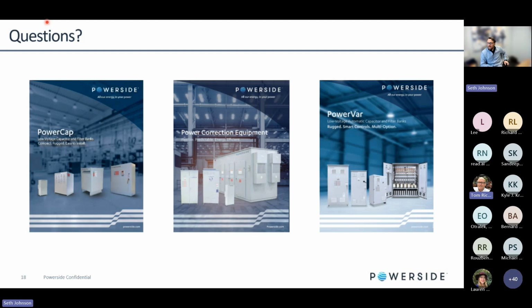Yeah, sure. Thanks for the question, Rick. It's going to depend on actually the size of the location. So IEEE has a standard called 1547 for inverter-based resources, which touches on this topic. It also touches on harmonics as well. Typically, people have used IEEE 519, but that's more from a load-based perspective or from a consumption perspective. But if you're actually using an inverter to bring power back to the grid, we're kind of widely adopting the standard of IEEE 1547.